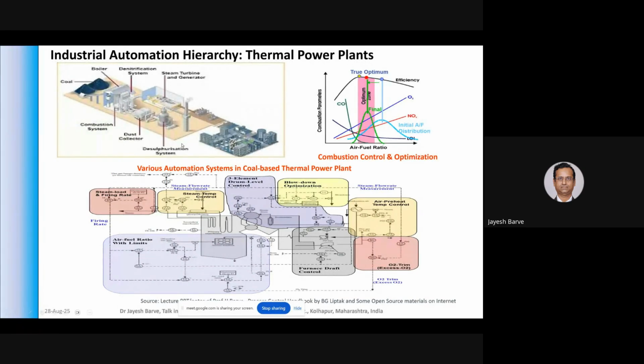Ultimately your interest is that load should be met efficiently and generation should be done efficiently. Anything that changes on the load side will change the current passing through the generator of the power plant. The generator will have a different current, so the back force created on the turbine will be different. Now the turbine is getting power from the steam, so my steam flow has to be changed. That means my boiler's thermal energy has to be balanced, so my coal and fuel flow should be changed. And as fuel changes, my airflow should be changed.